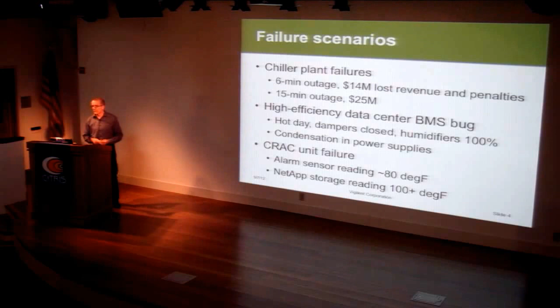So if you're an operator, what do you do? Well, typically they buy a lot more cooling than they need and run all of it all the time. That's basically this policy, the way I think of it: always on and always cold. They want to be blowing a lot of freezing cold air, so that even if something does fail, it's so cold that by the time it starts warming up to a temperature that's uncomfortable for the equipment, they've had time to react to it.